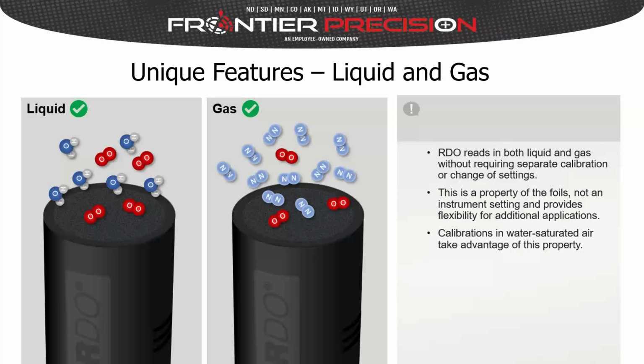Another unique feature, because of the formulation of that cap or the foil that's on the top, is that we can measure oxygen in both liquid and gases. I'm sure most of our customers are only interested in measuring in liquid, but the important thing is that you can actually calibrate this sensor using water-saturated air or air-saturated water and basically see no difference in the calibration and subsequent readings. So kind of an important property and a unique feature of the cap.